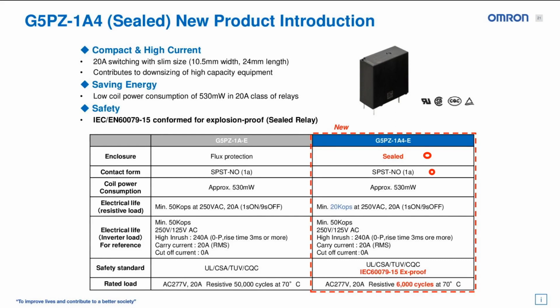It has 20,000 operations at that 20 amp 250 VAC. It has inverter load ratings as well for 50,000 operations, 250 V, high inrush of 240 amps with a make and break current of 0 amps. So if that is of a necessity to you, it has safety standards existing and then the improvement of the anti-explosion rating. And lastly, it is important to note that there will also be a 277 VAC rating for 6,000 cycles. So this product is already released and available if you have a 20 amp need.